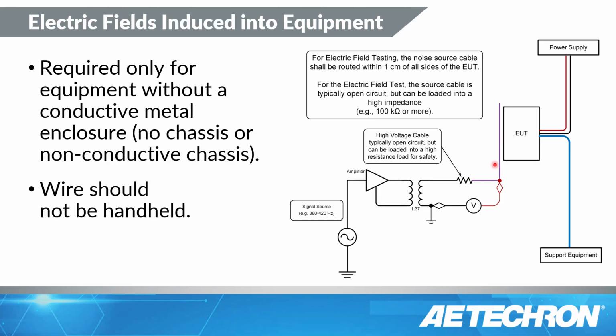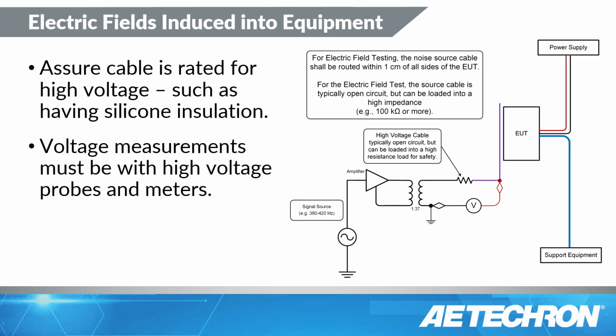Now, the best way I've seen this done is by using a high voltage wire, usually a silicone-based wire, and placing that inside, say, a plastic tube or taping it to a piece of wood or something, but ensuring that you have the end of it sealed off so that it isn't going to short to chassis, because you don't want to start inducing 170 volts of AC power in locations you're not going to be able to control. I do recommend using a silicone insulated wire. This is going to come in handy when we're doing some of our other testing. Most of these are capable of handling thousands of volts, so it should provide the safety you need for high voltage on this wire.